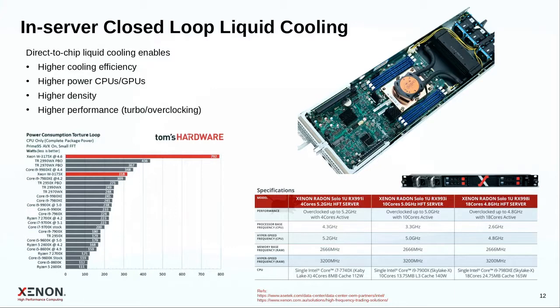We have the pump assembly on top of that. We're pumping the liquid through the tubing into a large heat exchanger, where that heat exchanger is obviously the biggest we can possibly fit into the package. In our case, for a standard 1U rack unit server, that heat exchanger covers almost the entire width of the system.